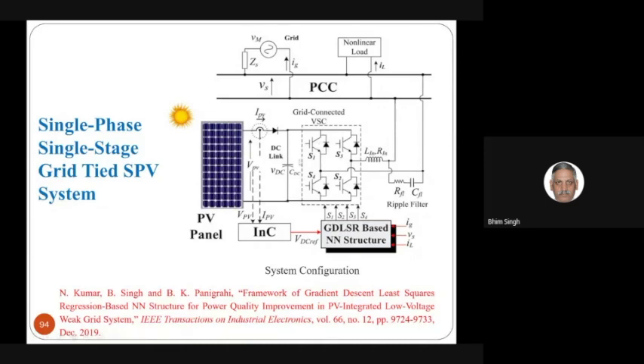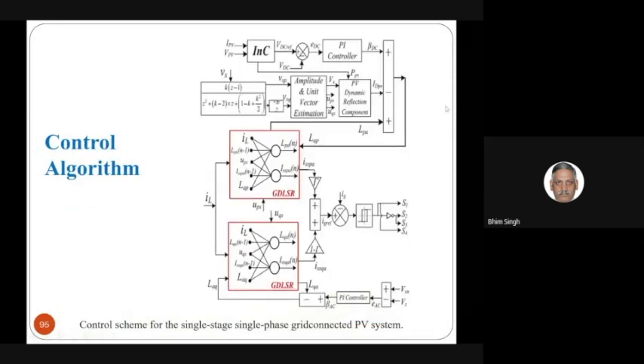So it's not only for maximum power taking or generation of solar power from the solar panel, but it also applies all the time for load compensation as well as for improving the power quality at the grid, and operates successfully even when there is a power quality problem in the grid, like voltage fluctuation or voltage distortion. So these are typical control schemes, because it's a single stage system.